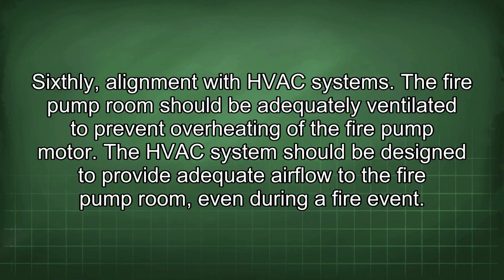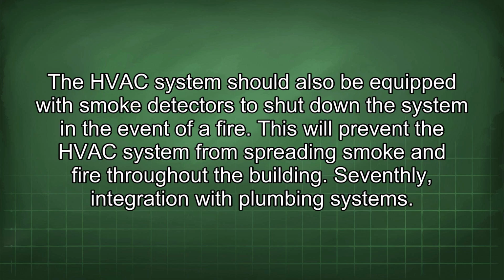Sixthly, alignment with HVAC systems. The fire pump room should be adequately ventilated to prevent overheating of the fire pump motor. The HVAC system should be designed to provide adequate airflow to the fire pump room even during a fire event. The HVAC system should also be equipped with smoke detectors to shut down the system in the event of a fire. This will prevent the HVAC system from spreading smoke and fire throughout the building.